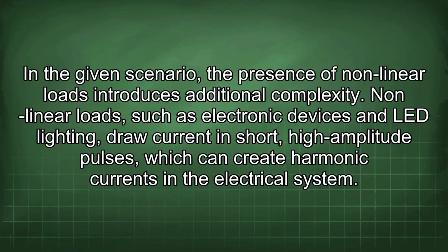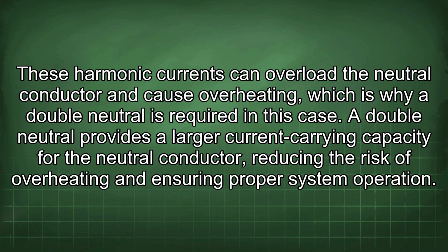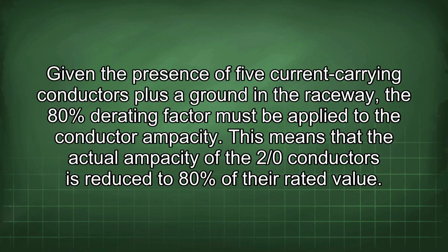In a given scenario, the presence of nonlinear loads introduces additional complexity. Nonlinear loads, such as electronic devices and LED lighting, draw current in short, high-amplitude pulses, which can create harmonic currents in the electrical system. These harmonic currents can overload the neutral conductor and cause overheating, which is why a double neutral is required in this case. A double neutral provides a larger current carrying capacity for the neutral conductor, reducing the risk of overheating and ensuring proper system operation. In the presence of 5 current carrying conductors plus a ground in the raceway, the 80% derating factor must be applied to the conductor ampacity.